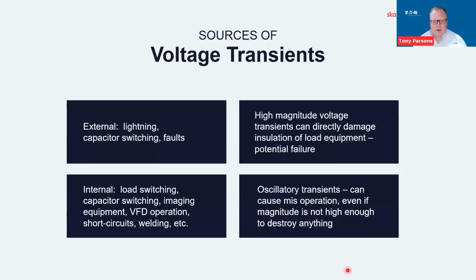So how do we fix these? I guess first, where do they come from? They can be both external and internal. External: lightning strikes on the system, capacitor switching on the utility system, or faults on their network. Internal: some of the same things, but also including the operation of the load equipment in the facility. We already mentioned welding. That can be another source. The transients can be problematic in a couple of ways. The high magnitudes of the voltage can directly damage insulation of load equipment, whether on circuit boards or even motor or transformer windings in some extreme cases. The oscillatory transients can cause misoperation even if the magnitude is not high enough to destroy anything.